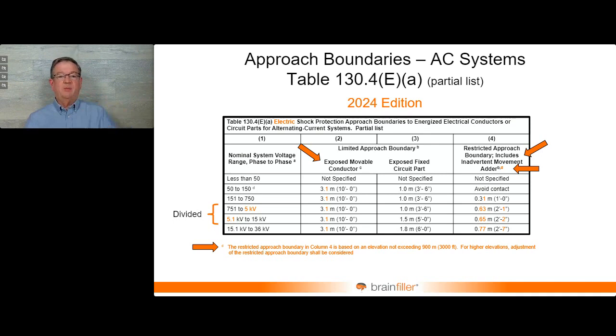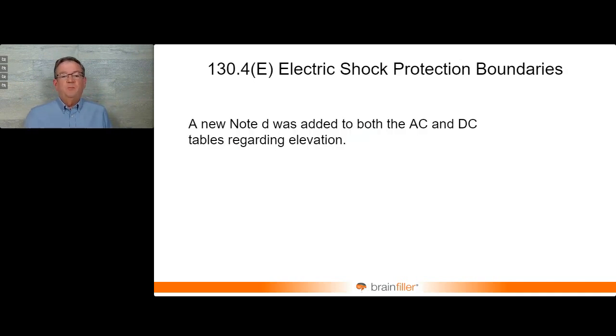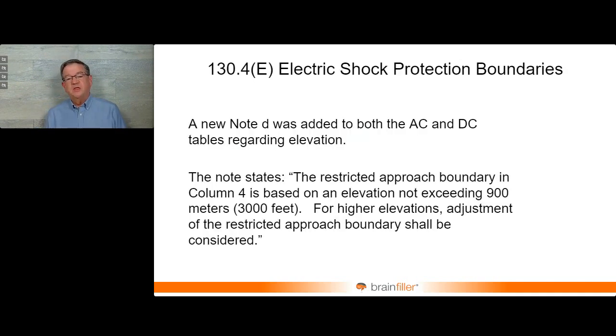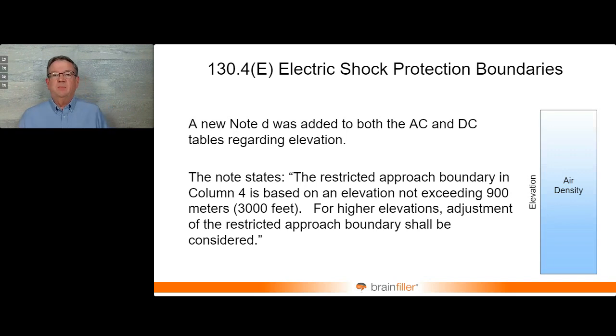Let me elaborate on this a little bit. This note says the restricted approach boundary is based on elevations not exceeding 3,000 feet. And for higher elevations, you may want to consider adjusting the distance. Now, it doesn't say you have to. It's just, here, this is something you may want to consider. What's the big deal about this? Well, at higher elevations, the air density becomes less.